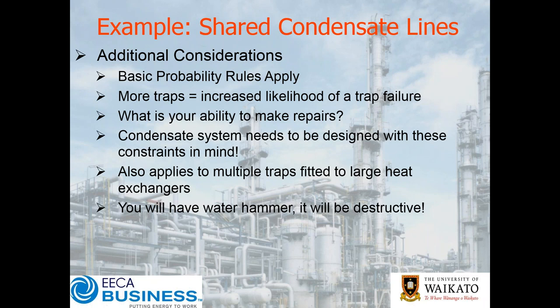Basic rules of probability apply: the more traps you have, the more increased likelihood of one of those traps failing. What you've got to consider is your ability to make repairs, and your condensate system also needs to be designed with these constraints in mind. When we talked about sizing the condensate line, if you need to tolerate a couple of traps failing — which is likely if you haven't got the right trap or it's not ideally installed — the likelihood all goes up. These are all extra risk factors to bear in mind. Ultimately, if you get these things wrong, you will have water hammer and it will be destructive.